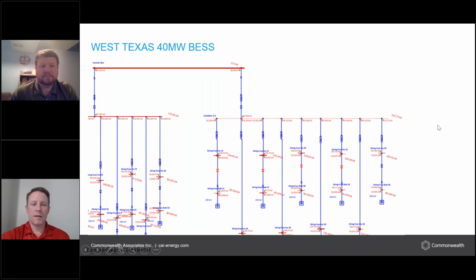So here is a printout of the DC short circuit current at that West Texas battery I was talking about. So up here at the inverters, it's incredibly high fault current at 173 kA. But if you look at the actual arc flash time, these fuses are incredibly fast. So the arc flash wouldn't have been very high here. Also down in the middle, I'm seeing about 118 kA there. The arc flash would not be significantly bad there either because all these fuses are so fast.